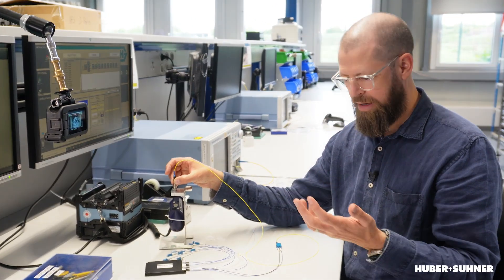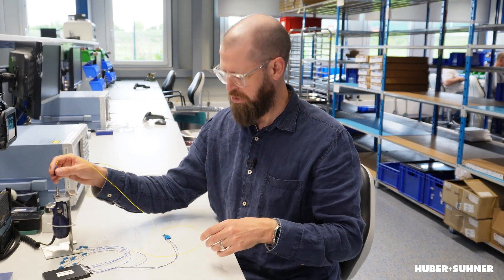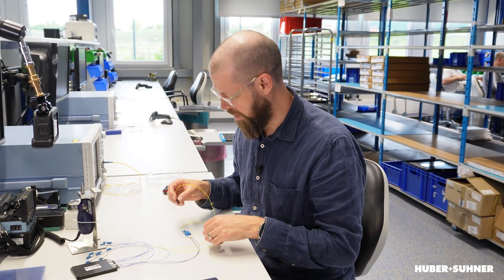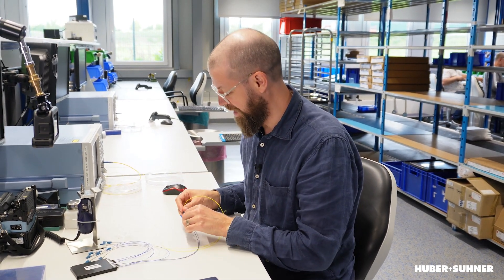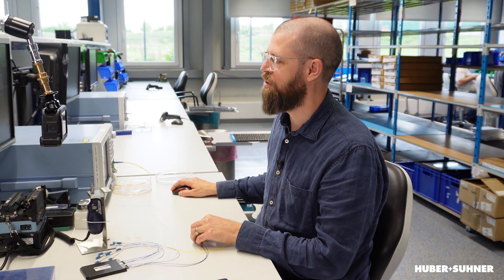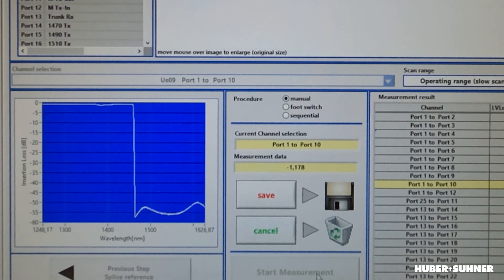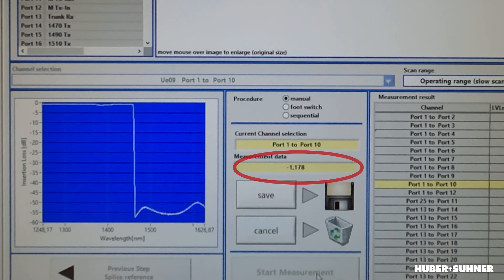Maybe we haven't got a cleaning tool around, so we think we'll just clean it on our shirt. I'll do that, reconnect it, do a new measurement — and sure enough it has improved, but we are still roughly 0.1 dB higher insertion loss.